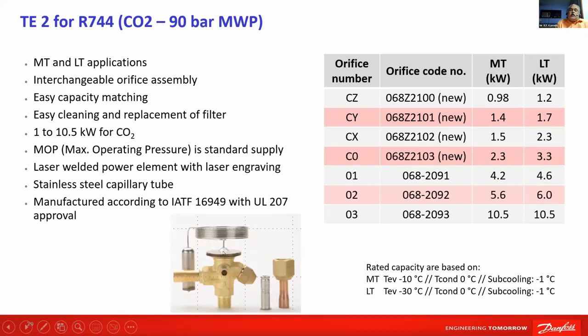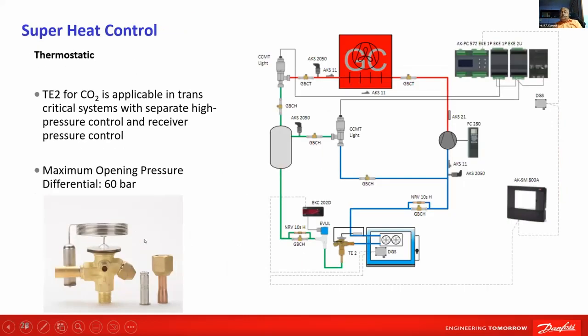Then, not so big, but the gas-liquid mixture inside this has to respond to CO2. That is the difference here. So it will operate in both subcritical and supercritical. If my system is operating supercritical, it will operate, and if the ambient temperature comes down to subcritical, the same system will also operate.